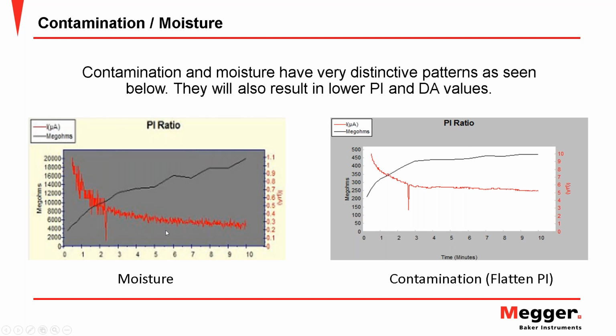Moisture, for one, has a telltale indication of oscillation. So the presence of moisture, because water is a dipole, right? The polar nature of the water molecule moving, flowing as it does in liquid form, that movement of charge causes it to oscillate. And so we see that up and down current. You could draw a line through that and you can see that we have a good PI here, the change in current over time, but these values can swing erratically quite a bit sometimes and could alter our PI readings.